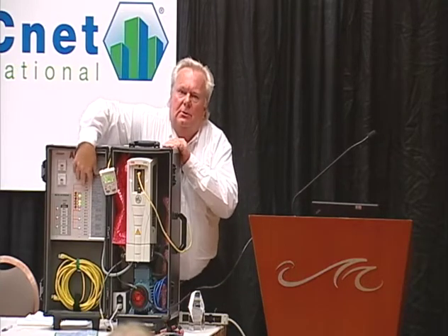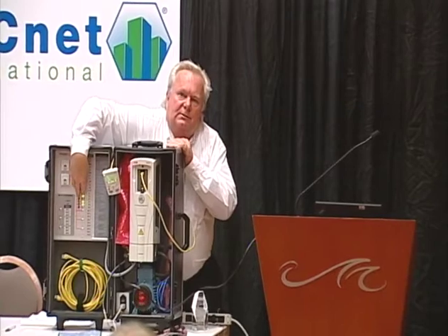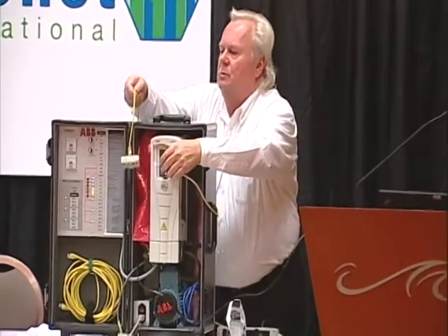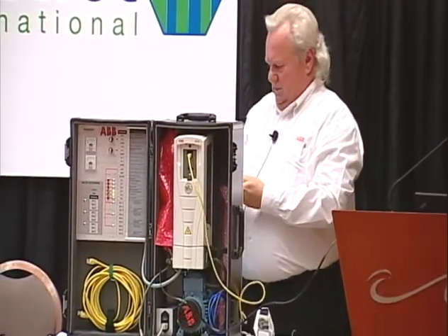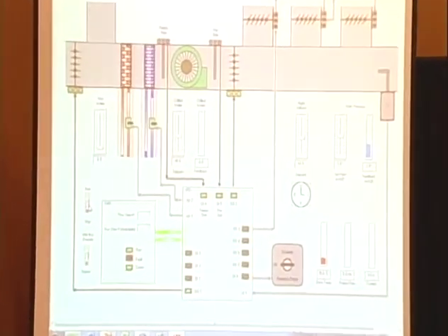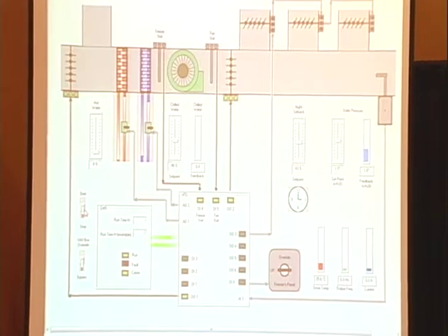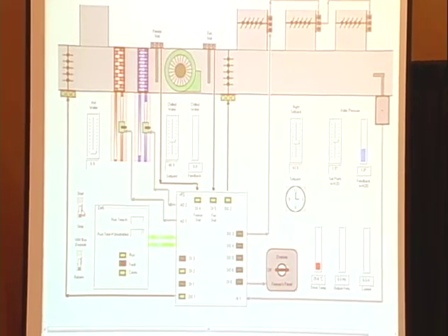So that's the kind of things I was showing the guys at this table in the construction trailer outside the hospital, is things we've been doing since 1994, is the easy start, stop, things like that. Another reason I want the damper control connected back to the VFD is, wrong way. Remember I said these drives have local hand buttons. So now if I push hand, first thing that's gonna happen is I'm gonna fire the relays to open those dampers again, and it won't run until the damper proof comes back, the end switch comes back to the drive, and now I got control of speed here, I'm at 0 hertz, I'll ramp it up.